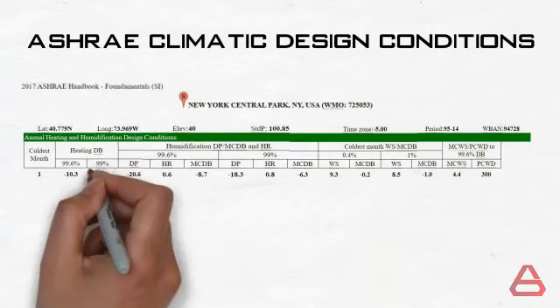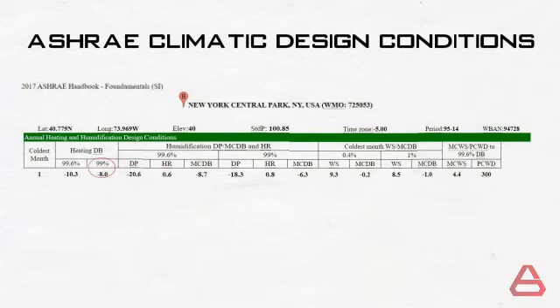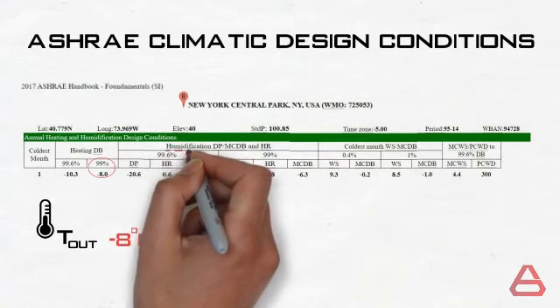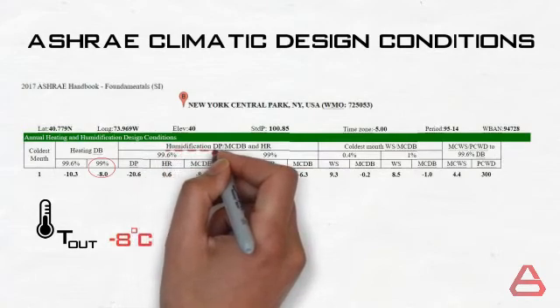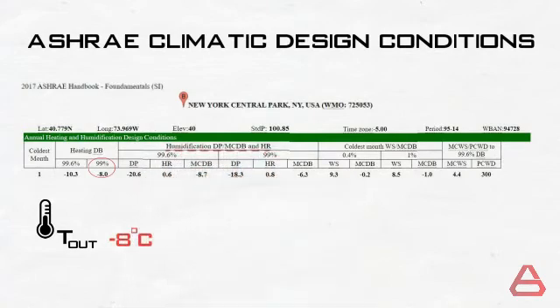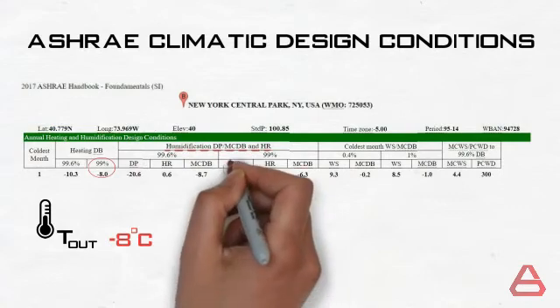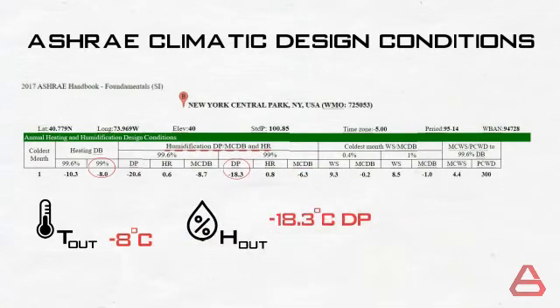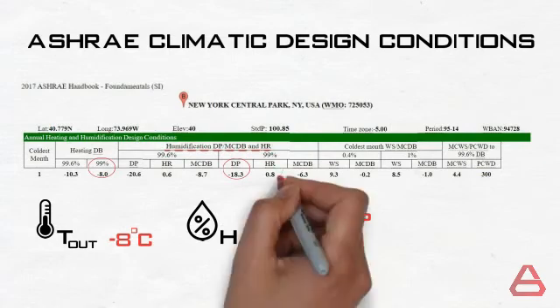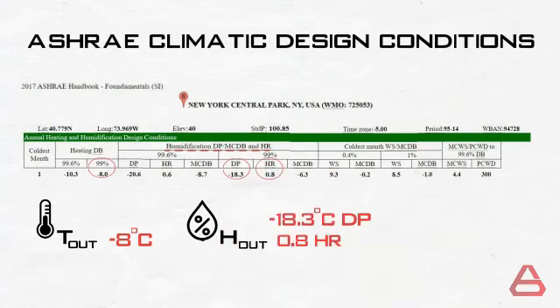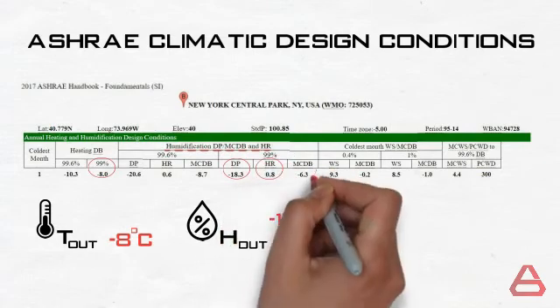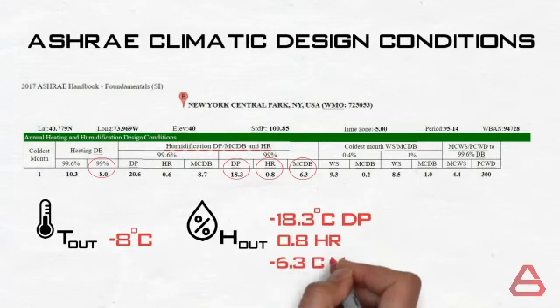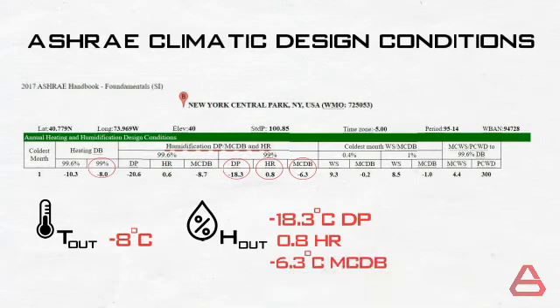The first table that appears that is titled annual heating and humidification design conditions is the one we need. This right here, under heating dry bulb 99th percentile, is our heating outdoor design dry bulb temperature, which is minus 8 degrees Celsius. For humidification, we head to the humidity subtitle and select the 99th percentile values, which are a dew point of minus 18.3 degrees Celsius, a humidity ratio of 0.8, and a mean coincident dry bulb temperature of minus 6.3 degrees Celsius.